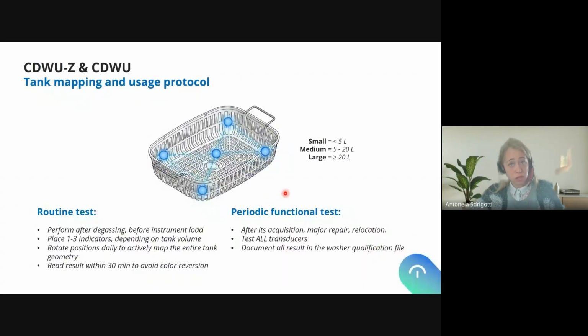And the periodic functional tests after acquisition, major repair, relocation, okay? In the periodic functional test, we have to test all transducers. If we have 12 transducers, we have to locate one indicator on top of every transducer. How do we know this? Because we have the manual of the ultrasonic washer. The manual will display precisely where every transducer is located. Okay, this is mandatory information from the ultrasonic washer manufacturer. And of course, we have to document all the results in the qualification protocol or file. Okay, so this is how we use it.